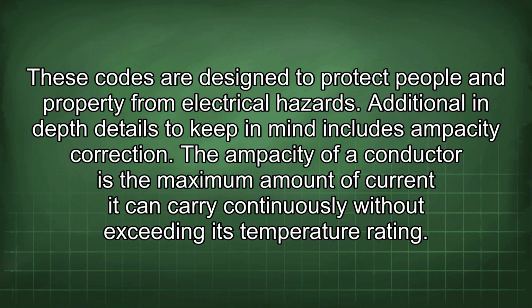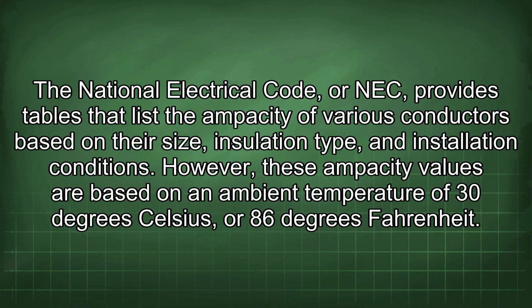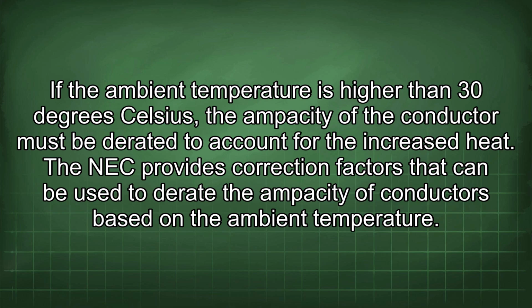Additional in-depth details to keep in mind include ampacity correction. The ampacity of a conductor is the maximum amount of current it can carry continuously without exceeding its temperature rating. The National Electrical Code, or NEC, provides tables that list the ampacity of various conductors based on their size, insulation type, and installation conditions. However, these ampacity values are based on an ambient temperature of 30 degrees Celsius or 86 degrees Fahrenheit. If the ambient temperature is higher than 30 degrees Celsius, the ampacity of the conductor must be derated to account for the increased heat.